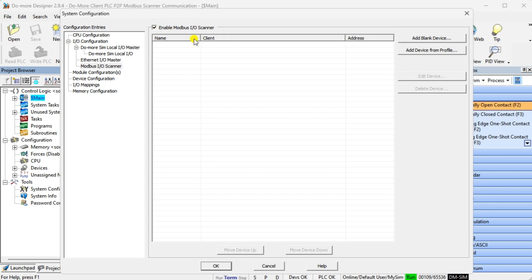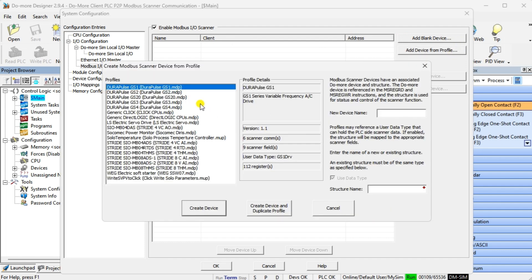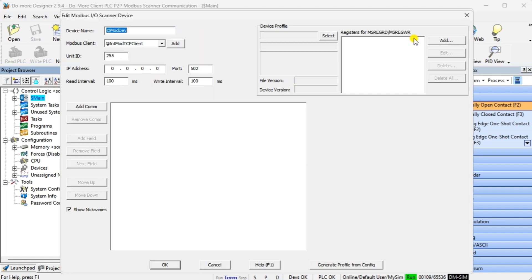On the right side of the window you will see two options. Add Device from Profile will show you devices that have been pre-programmed so you can communicate with different equipment — we demonstrated this before when communicating with the Solo process temperature controller. Select Add Blank Device, then enter the IP address of the server PLC. We will also change the read and write intervals to the minimum time, which is one millisecond.